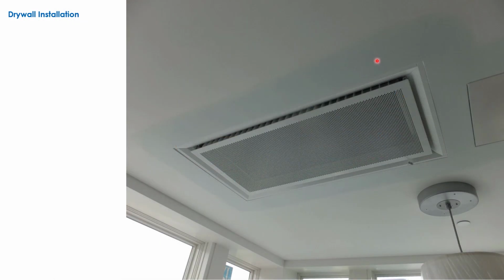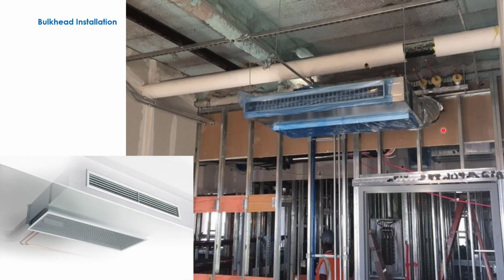Now here's a chill beam that's been drywalled into a ceiling, and they can come with what we call a plaster flange for all different kinds of beams. But immediately you're going to need a service access section over here to allow you to get up to service the valves and be able to shut off the isolation valves to this beam if you ever needed to service it or do anything as well. So something you have to consider in the layout is that these beams need to be located someplace where you can service the valves.